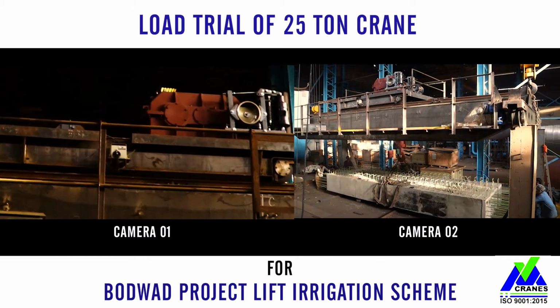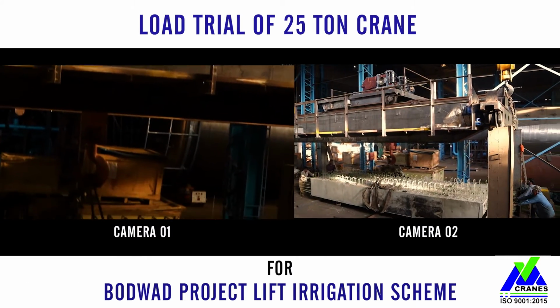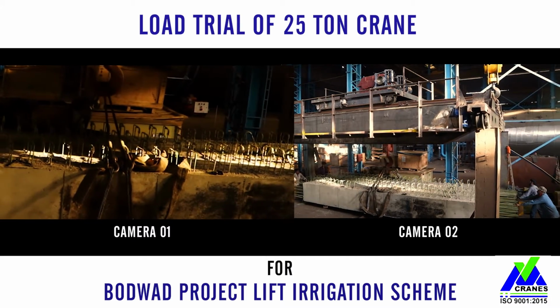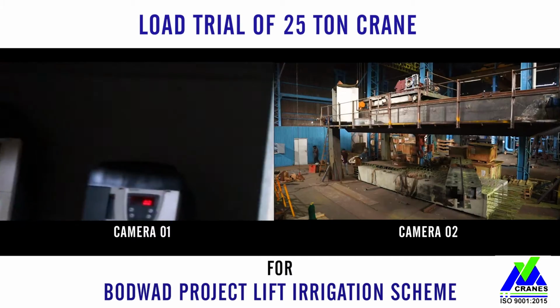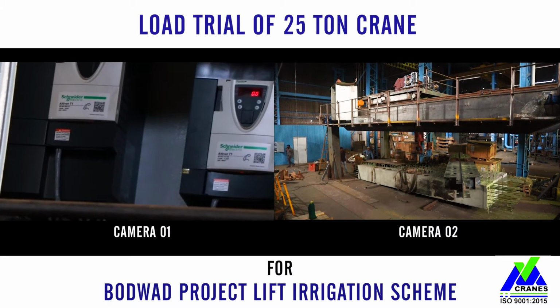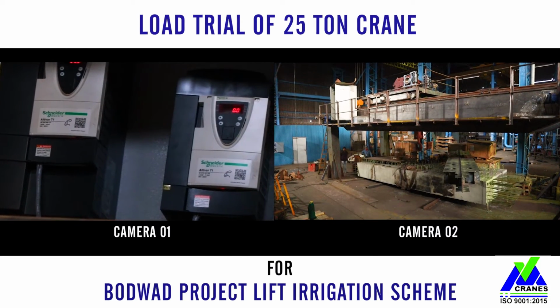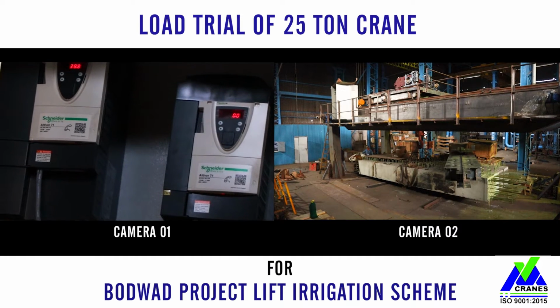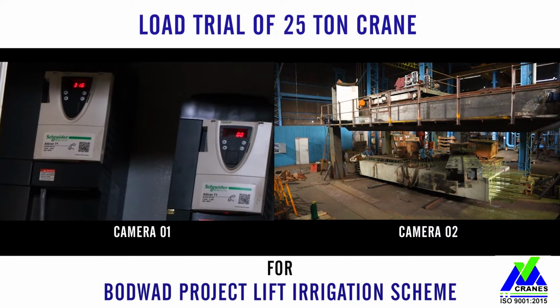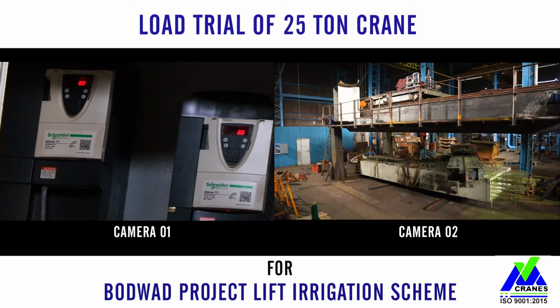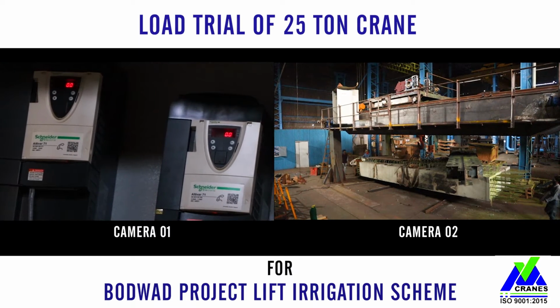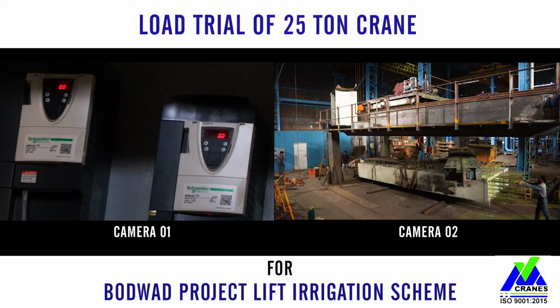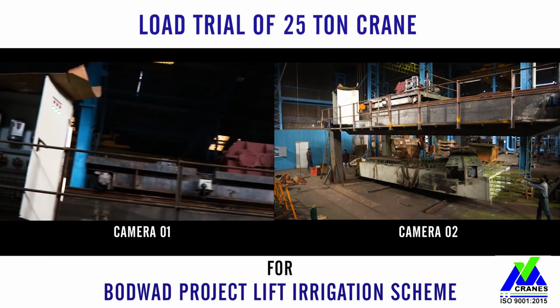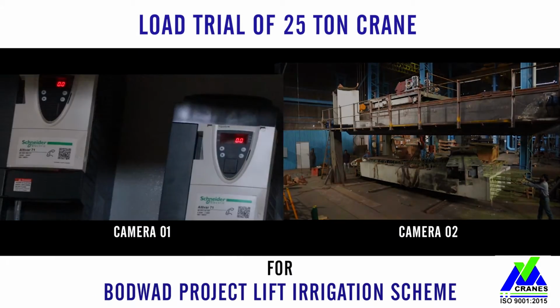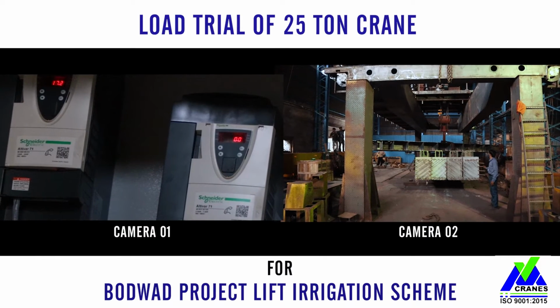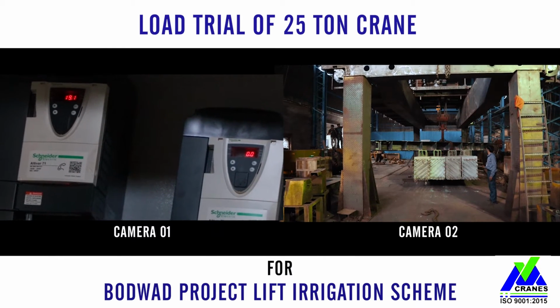Now the movement has been completed and we are again going to overload the crane with additional load of say around 6,300 kg, the total becoming 31 tons approximately. Now with the overload of 31 tons, we are just lifting the main hoist motion. We are lifting the load on overload and then we will be again keeping it down.